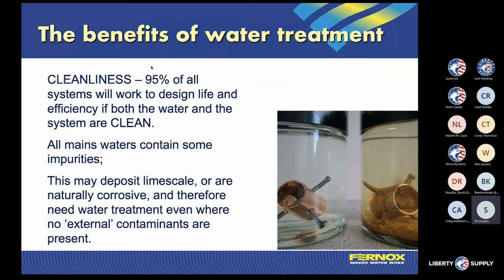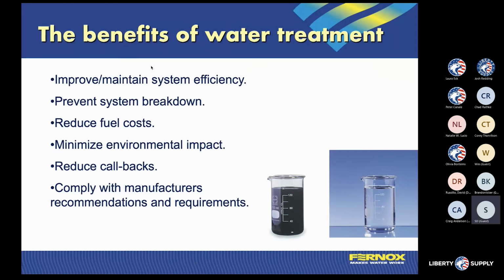And we want to have system water that isn't black or brown or different colors. It should be clear, if it's the water solution that you started with. When you drain that system out or flush it down, it shouldn't have deposits or colors in it. And that's part of this process when we're talking about doing our water treatment. The benefits of water treatment are going to reduce your downtime. You're not going to get that middle-of-winter breakdown where you have a system that's completely down. It's never at the ideal time. So it's going to reduce your maintenance, your downtime, and callbacks with your customers.